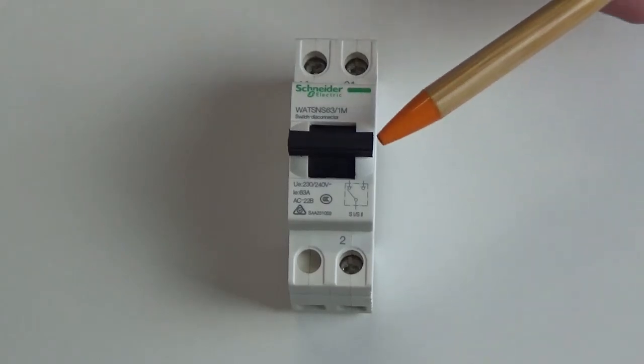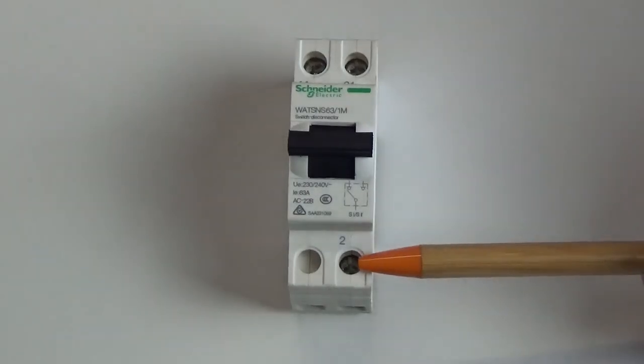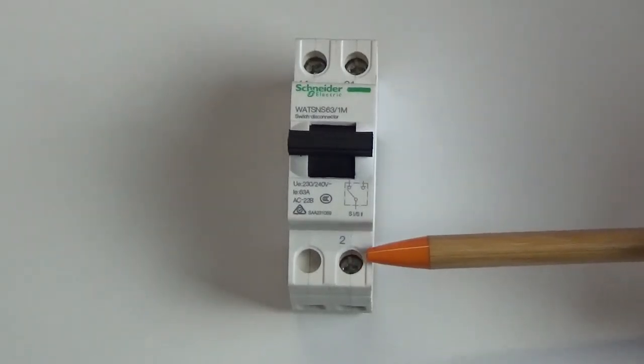You put the switch, the changeover switch, into the off position in the middle. This is the backup port going out to the backup loads. That should go dead. If it's got power in it, you've wired it wrong.